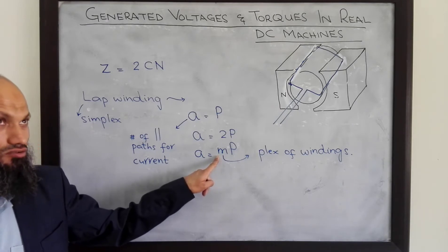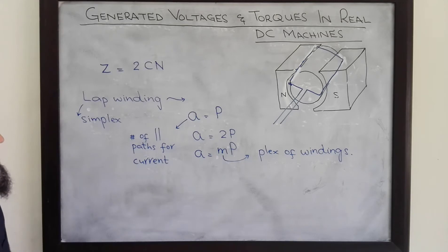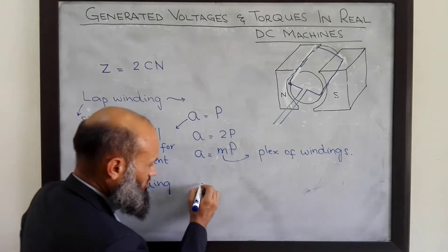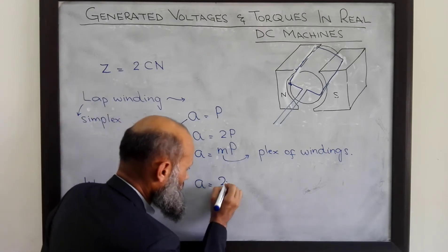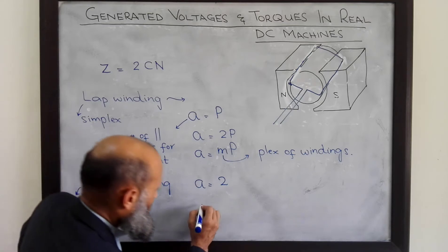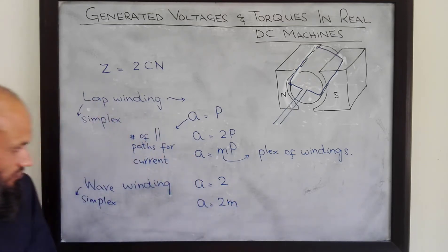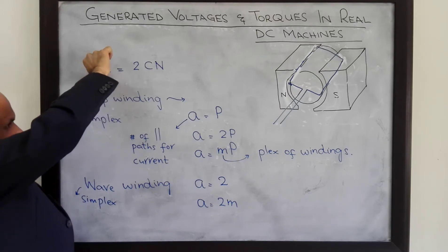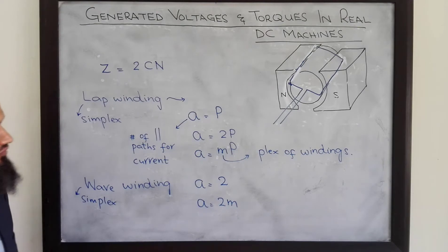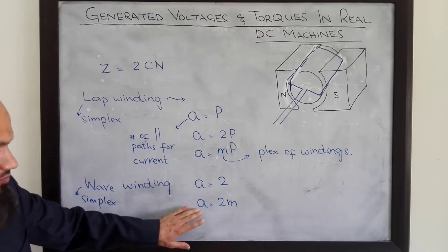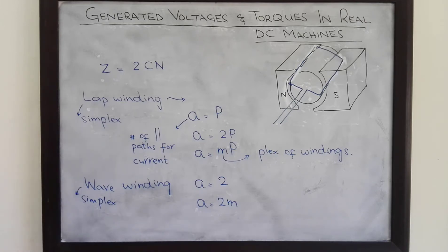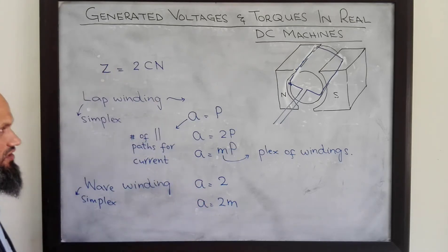For duplex winding M is 2, for triplex winding M is 3. In the case of simplex wave-wound DC machines, the number of parallel paths for current is always equal to 2. For duplex and M-plex wave winding, the number of parallel paths is 2 multiplied by M. So there are Z conductors in the real DC machine in which voltage is being induced, and there are A parallel paths. The total number of conductors in each parallel path is Z divided by A.